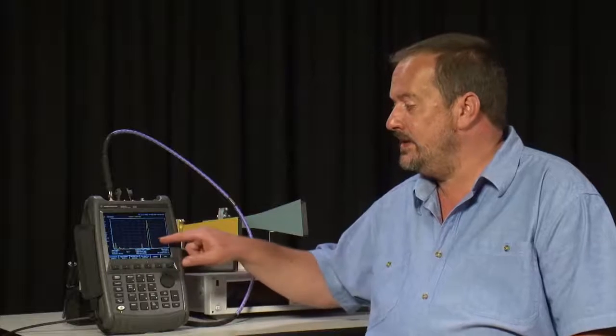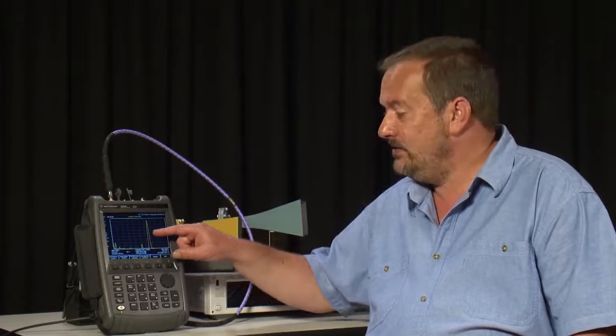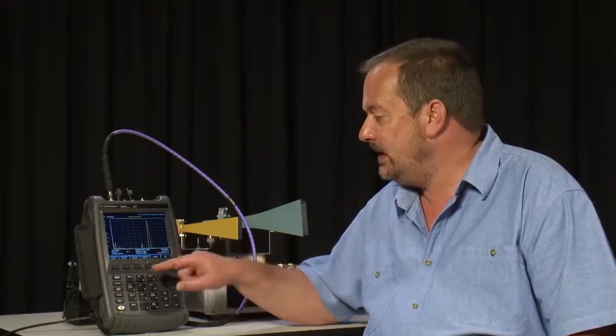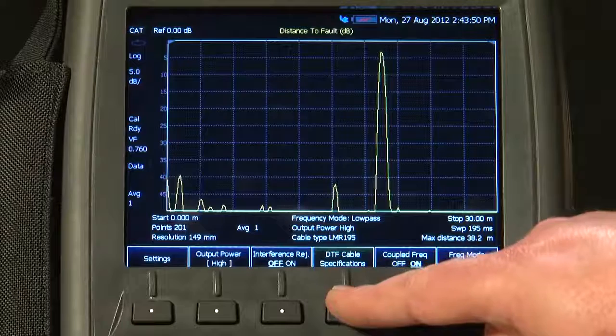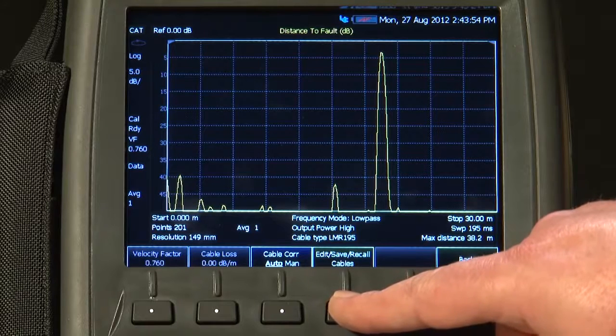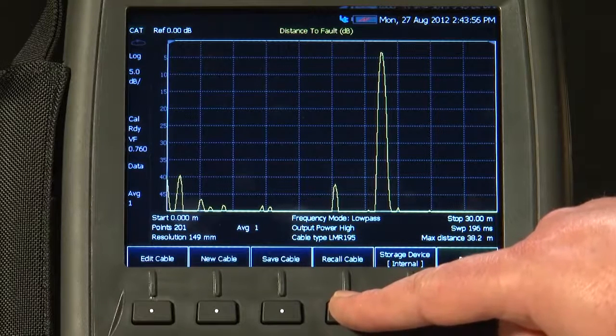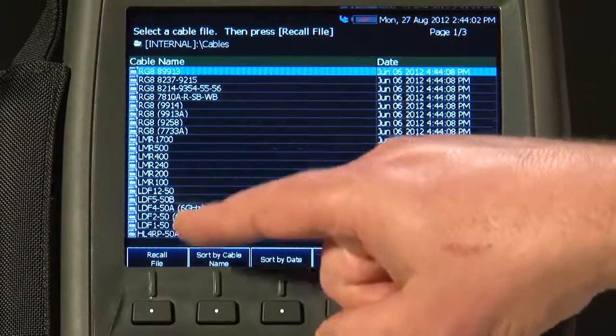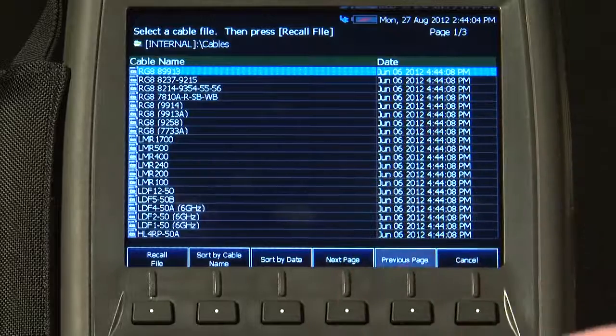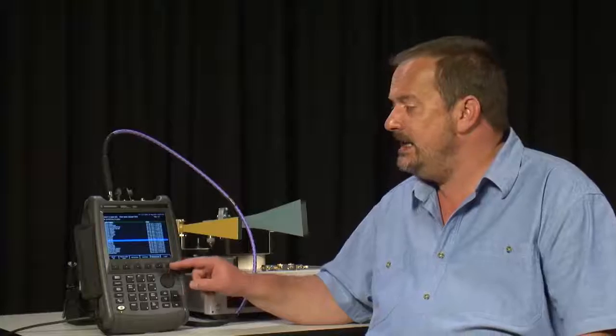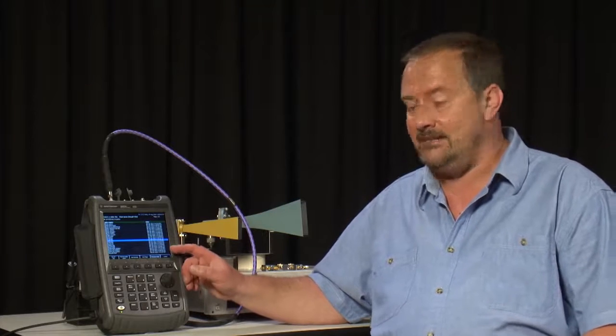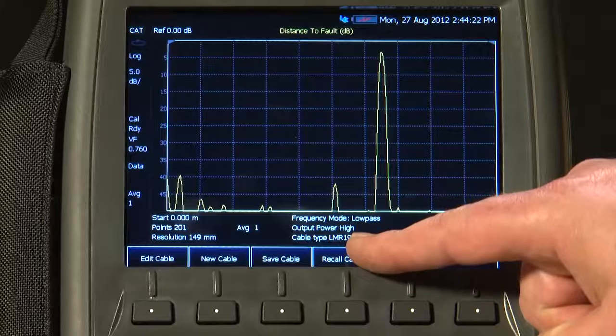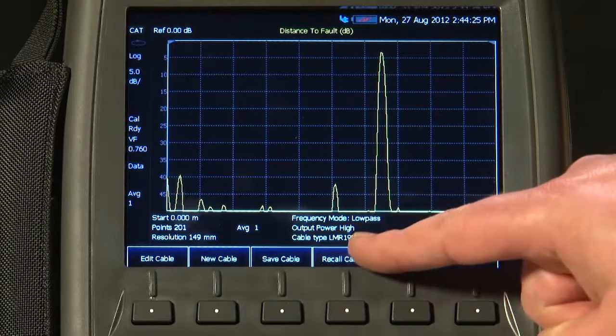Now, to ensure that the Distance measurements and Return Loss measurements are accurate, you will know that we have to tell the FieldFox what type of RF cable we are using. So if I press the Measure Setup button and DTF Cable Specifications, and then Edit Save Recall Cables, you will see we can recall a predefined cable, an RG8 or one of the LMR standards or LDF standards, directly from the FieldFox's memory. And if the cable you are measuring is not in the list, you can simply add it by entering the Velocity Factor and Loss values. You will see here, I have selected the cable type of LMR 195.